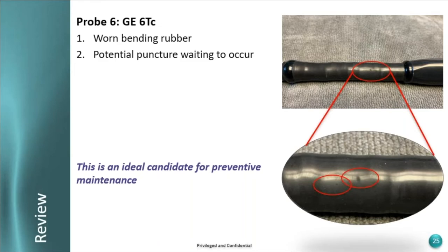With these preventative maintenances, one of the things that we do is we do not want to issue a loaner, because if we issue a loaner, there's a chance that loaner may be damaged, and then I have to bill you twice. I have to bill you for your probe, and then I have to bill you for damaging my loaner, which I hate those conversations, and everybody does, nobody likes them. So what we do is if we get a probe in for preventative maintenance, that probe is prioritized. It takes us about a day to do the preventative maintenance and we can get it back to you.